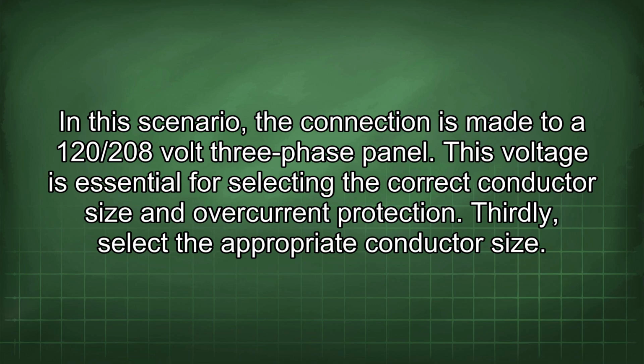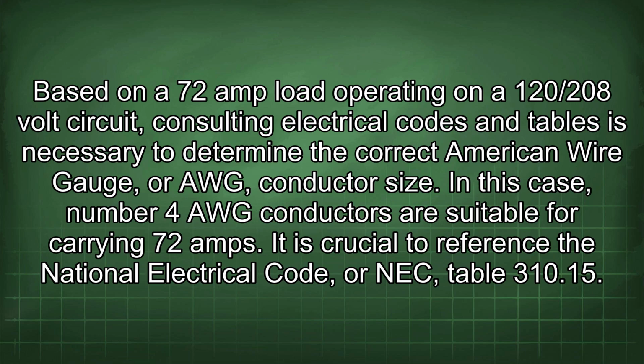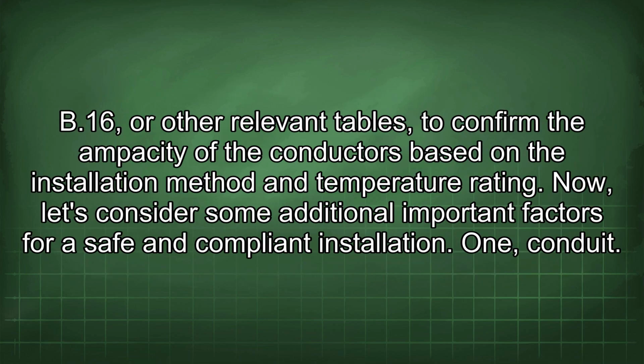Thirdly, select the appropriate conductor size. Based on a 72 amp load operating on a 120/208 volt circuit, consulting electrical codes and tables is necessary to determine the correct American wire gauge, or conductor size. In this case, number 4 AWG conductors are suitable for carrying 72 amps. It is crucial to reference the National Electrical Code, or NEC, Table 310.15(B)(16), or other relevant tables to confirm the ampacity of the conductors based on the installation method and temperature rating.